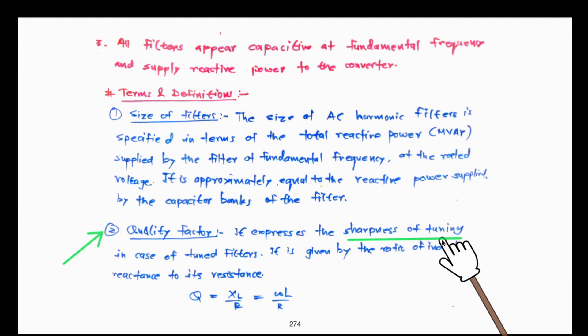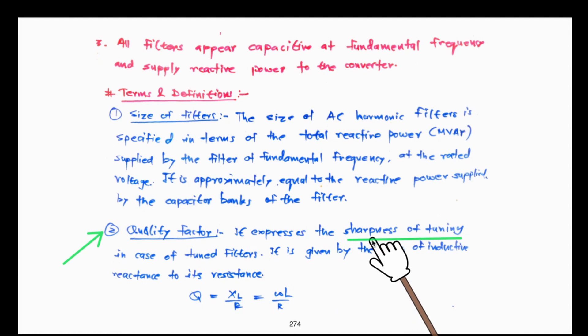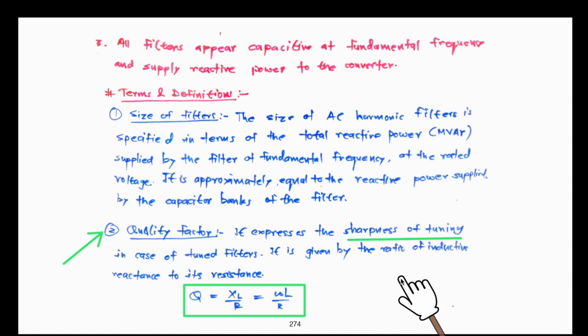All harmonics are present — fundamental, 11th, 13th, 23rd, 25th — but a single-tuned filter for the 11th harmonic must be able to identify and select only that frequency. The Q factor is obtained as the ratio of inductive reactance to resistance: Q = ωL/R, or X_L/R. A diagram on the next slide will provide a better understanding of the Q factor.